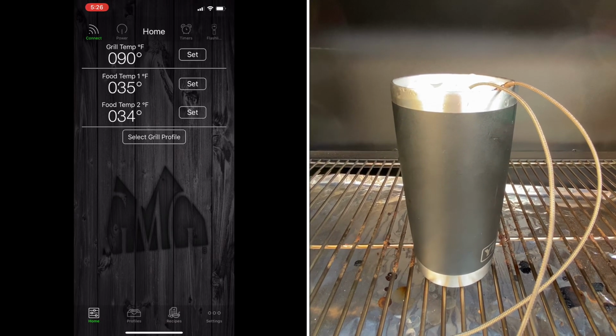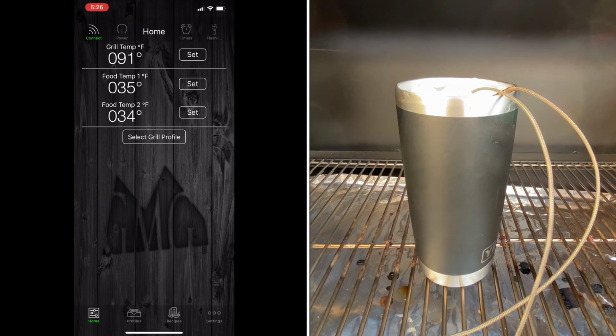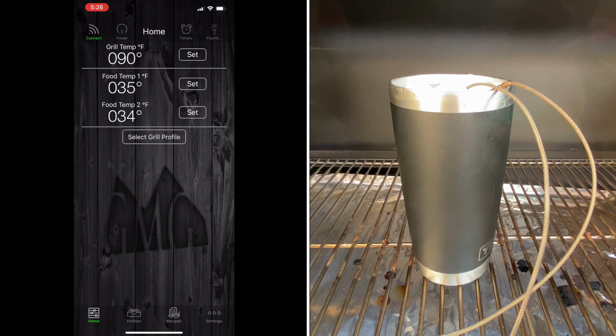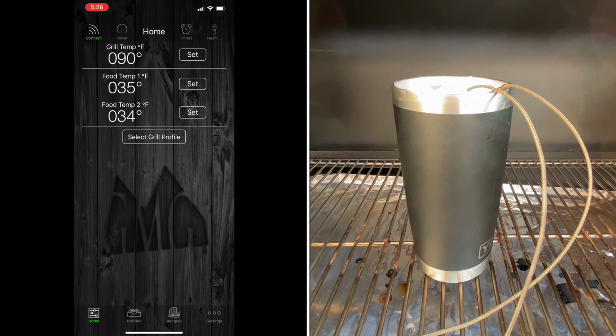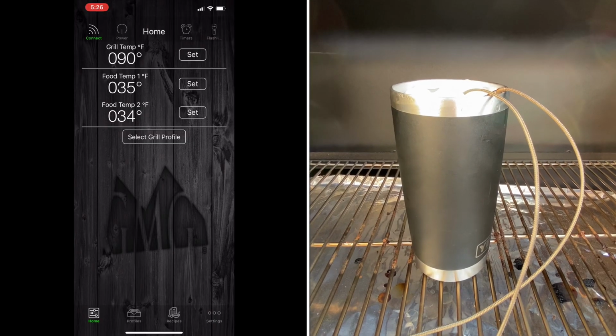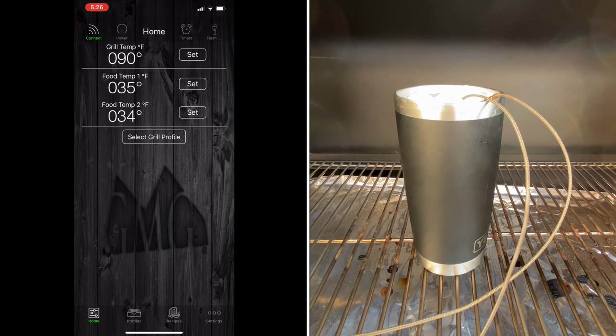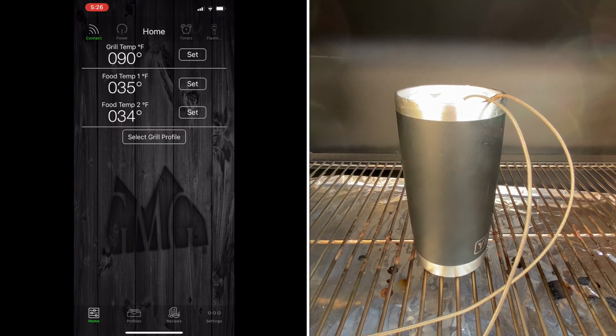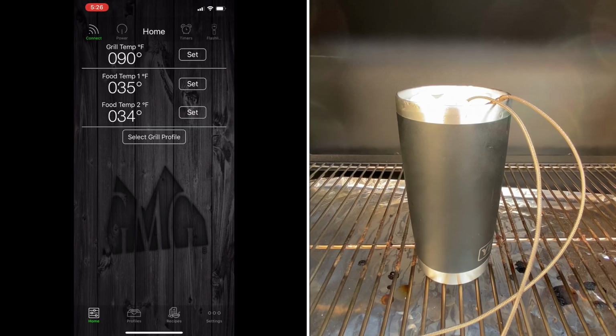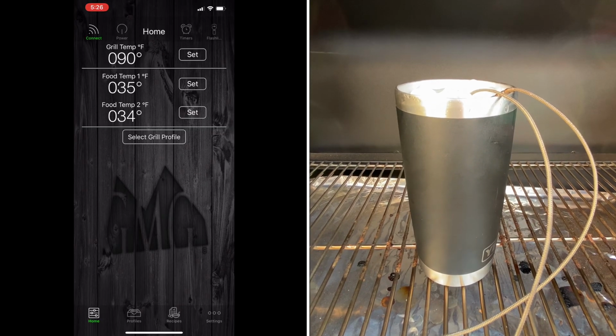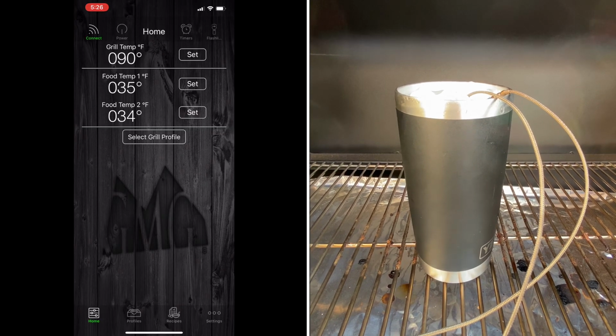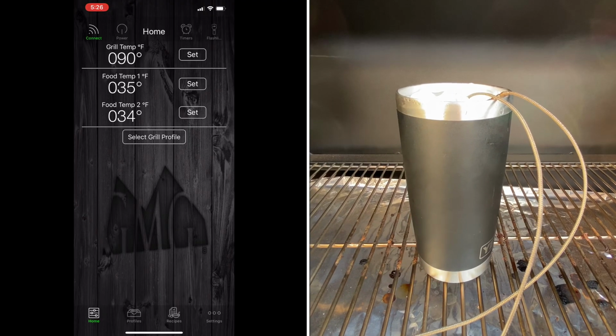Alright, now you can see my food probe temp 1 and food probe temp 2. One's 35 degrees, one's 34 degrees. We know that in an ice bath, we should be at 32 degrees. So now all you want to do is record the offset value of each probe. 35 degrees is 3 degrees off, 34 degrees is 2 degrees off, and they're both high.